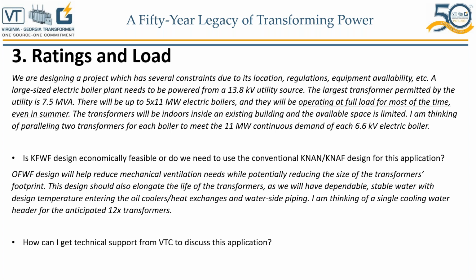The next one. The question starts with a comment. We are designing a project which has several constraints due to its location, regulations, equipment availability, etc. A large-size electric boiler plant needs to be powered from a 13.8 kV utility source. The largest transformer permitted by the utility is 7.5 MVA. Okay, I don't know why they would just do that, but let's go with that. There will be 5 11 megawatt electric boilers. So I think the total energy needed is 55 megawatts, right? So you're only limited with having all the way up to 7.5 MVA.